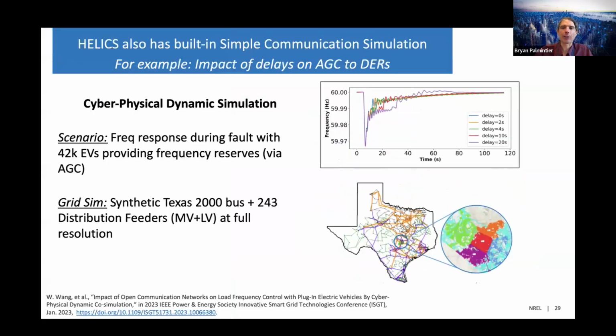Like in this example, we're looking across a couple of minutes of time, where that delay becomes relevant in perhaps not as carefully designed systems, where there may be either bandwidth bottlenecks or so many handoffs between, say, a market operator sending signals out through some gateway, AGC, connecting into the aggregator. They have to churn it and then pass it through another network. Maybe the utility gets involved, and somewhere down the line, it's working on the backbones of either interconnections or internet connections, but for customers or other devices.